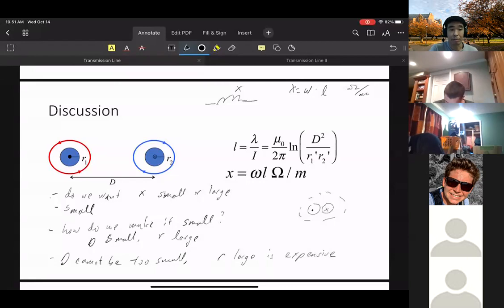And normally there'll be some reactance left over, so normally we cannot ignore the reactance on the line. There's some value, and this value is typically not too small, because of this equation. Because we've separated out the wires, and R is fundamentally not a very large value. We cannot build it to be very large. So the thing to remember is that when you engineer wires, we'll engineer this value to be as small as possible, but typically this will dominate the R term. R is typically much smaller than X in per unit terms.